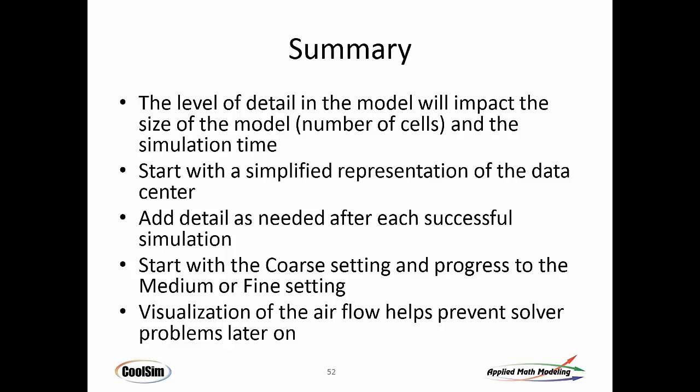First I check the summary report, the text, just to make sure the input parameters were correct, that the CRACs were set up correctly, that the IT load in the racks were set up correctly. Then I look at the airflow visualization to make sure there's no issues with air not getting to where it's supposed to get. Those are the path line plots I was showing you. And it allows you to see what's going on and make sure the air is moving to where it needs to go.